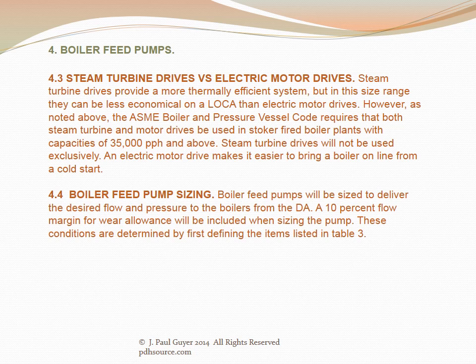Steam turbine drives provide a more thermally efficient system, but in this size range they can be less economical on an LCCA than electric motor drives. However, the ASME boiler and pressure vessel code requires that both steam turbine and motor drives be used in stoker-fired boiler plants with capacities of 35,000 pph and above. Steam turbine drives will not be used exclusively, as an electric motor drive makes it easier to bring a boiler online from a cold start. Boiler feed pumps will be sized to deliver the desired flow and pressure to the boilers from the deaerator, with a 10 percent flow margin for wear allowance included.